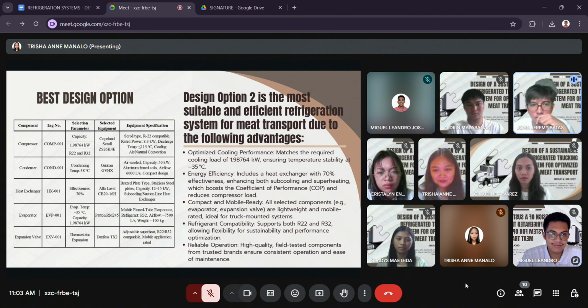While this does indicate a significant energy input, it ensures that the refrigerant is circulated effectively, contributing to the system's reliability. The system's coefficient of performance is calculated at 0.3357, which may seem lower than ideal. However, the design compensates for this through the inclusion of a heat exchanger. This feature enhances both subcooling and superheating processes, helping to optimize thermal performance even with the moderate energy efficiency.